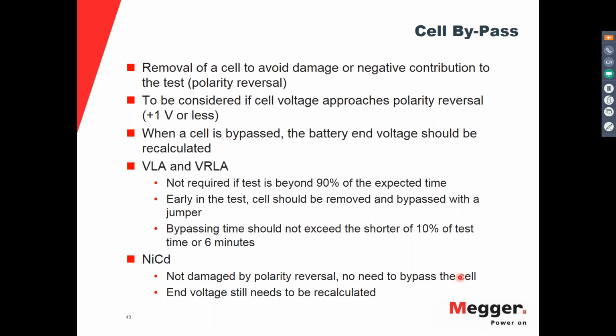For the VLA and the VRLA batteries, it is not required if the test is beyond 90% of the expected time. But if this happens early in the test, the cell should be removed and bypassed with a jumper. And this means that if you can, because you have very short time, you should not exceed more than 10% of the duration of the test or 6 minutes, whichever is shorter.